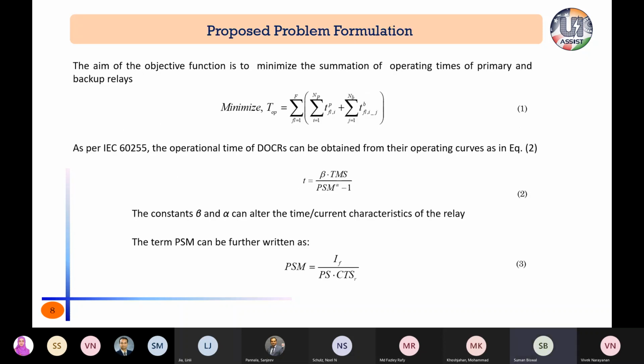Then our proposed problem, the relay coordination problem or the protection coordination problem, can be formulated as an optimization problem. Here we are going to minimize the summation of all the operating times of primary and backup relays. For example, the first term in the bracket is a primary relay. So T_FLI, this is the fault at location I, with subscript P, that is the primary relay. For each primary relay, we have one or many backups. So we have to take care of all the primary-backup relay combinations and also the various fault locations. So this is our objective function that we are going to minimize.